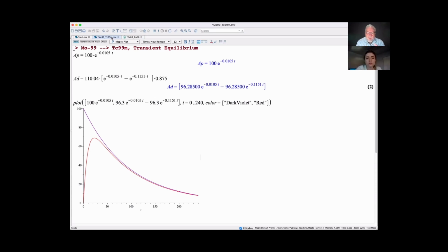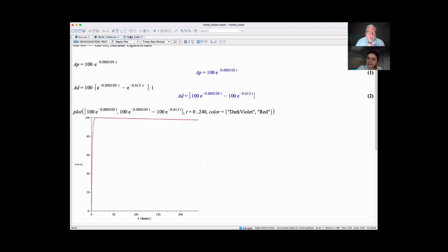So in the chemistry and the way everything is synthesized, there's always going to be a loss of product. So the important thing is, when you're looking at generators, and we did this for gallium, the gallium-68 generator, we looked at in practice, what is the yield? In some instances, the yield is between 50 and 60%. So we're seeing 50 to 60% less than what's predicted.